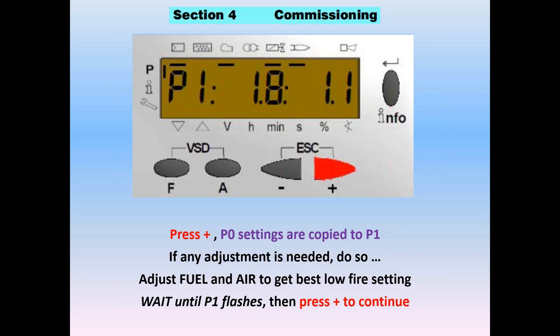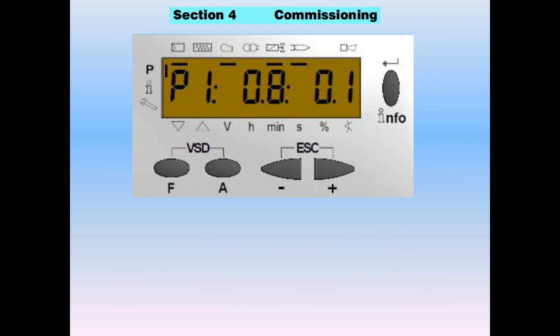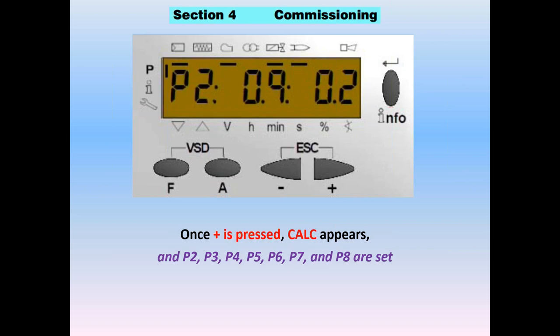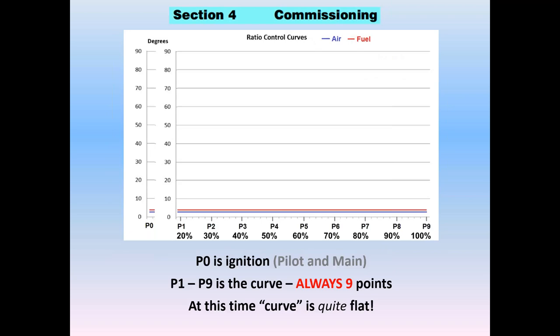Once you get to P1, you may want to dial this down so that when you release to modulate, you get the full benefit of the turndown of the burner. Whatever your maximum turndown is, that's what you set for P1. Once you have settings of P1 in, press plus. A 'calc' will appear — it has now calculated P2, 3, 4, 5, 6, 7, and 8 in a straight line to the P9 you already had. So P2 is virtually the same because we have a very flat curve. P0 is the ignition settings, P1 was the same with minor changes, P9 was our initial flat settings.